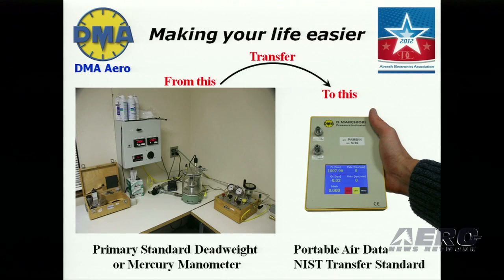Air data test instruments all require a minimum of 12 months calibration, and traditionally this is referenced back to a laboratory-based primary standard such as a deadweight tester, shown here on the left, or a mercury manometer. While the PAMB cannot be seen to replace the primary standard, it can act as a transfer standard, making the actual calibration or validation of the air data tester much simpler.